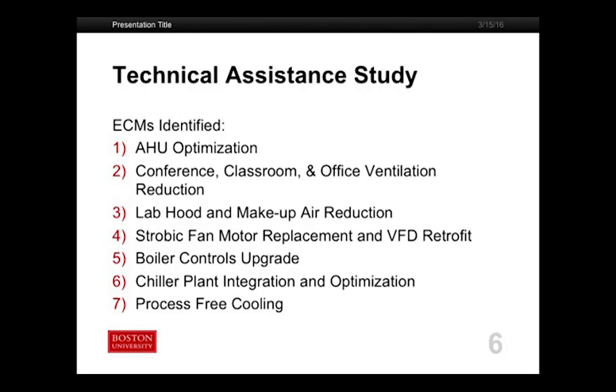And I think the details on that, if I remember, was that the minimum set up in 1995 was about 50% of peak for your CFM on your boxes. And so we were able to quickly reduce that to 30% of peak, and then there was no schedule for the conference classrooms or offices, so we just let it rip. And now in unoccupied times, those supplies shut off completely. I'm getting the hook here.